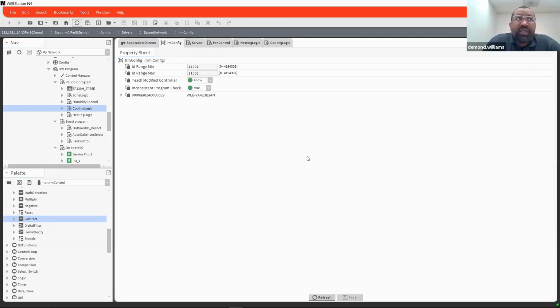So like I say, with the reset, it's basically dealing with the power feature. So it looks at the service button before the program actually starts up in the controller. So if you power it up while you're holding the button and it's held for a couple of seconds before it officially starts the program, then it knows that you want it to actually wipe your controller.